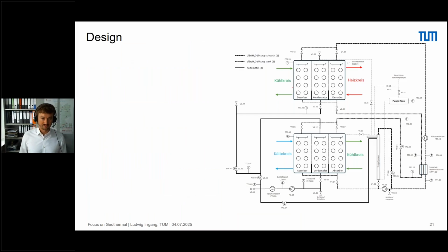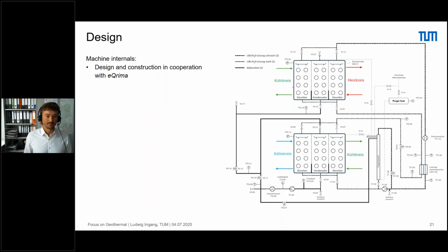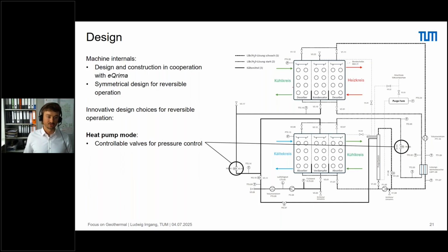I want to shortly go over the innovative ideas that we realized in the machine. So for the construction and design, we have a partner, which is eQrima. They are a very young absorption chiller and heat pump company, and so they allowed us to have a lot of changes in the layout of the machine. So that's what I want to show now. We have a symmetrical design of the two pressure stages, which is good for the reversible operation. And for the heat pump mode, we included controllable valves between the two pressure stages, because we will have very different pressures in the high and low pressure part, and we have to control for the pressure.